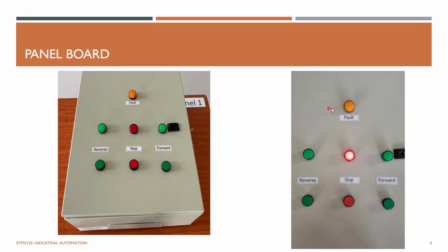In the event of a fault, this yellow lamp should light up. For example, in our motor overload event, this fault light should indicate. If there's a fault, you are not allowed to run the motor unless the fault is cleared. As well, when you run the motor in the reverse direction, this reverse lamp should light up.